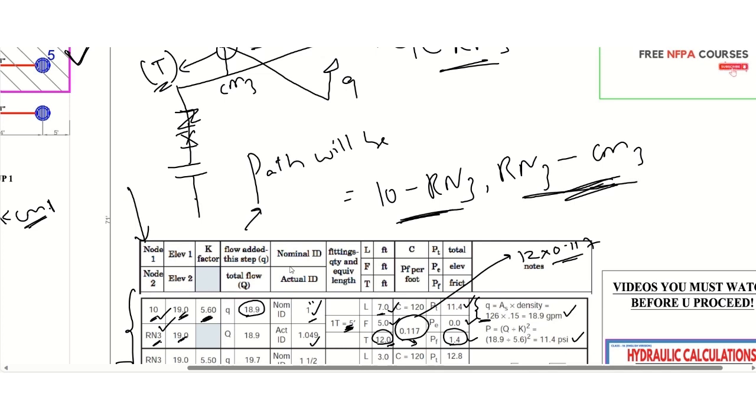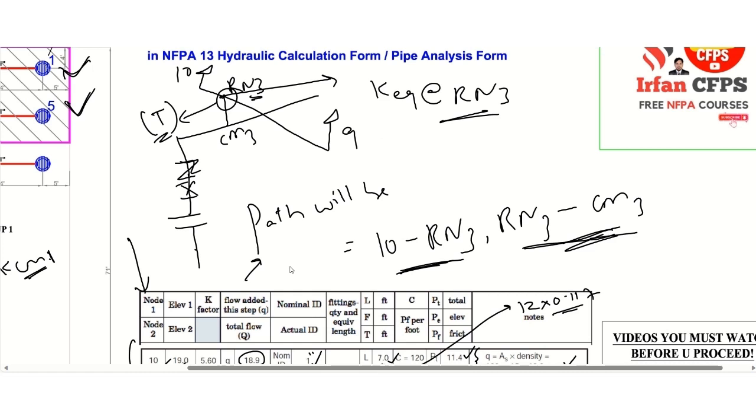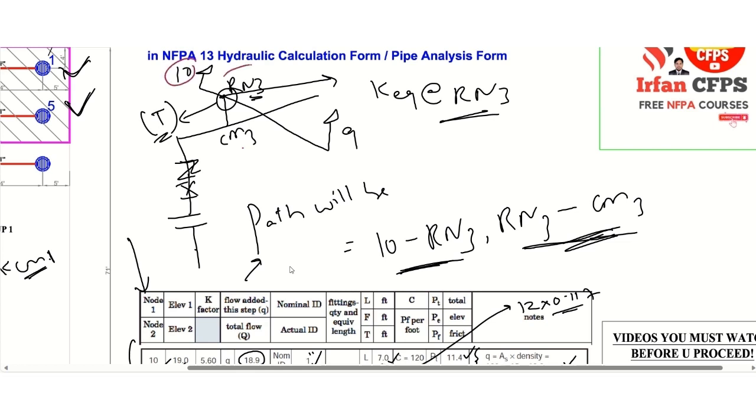So now what we need to do, since we are considering the most challenging path from 10 to RN3, we are going to come back to the primary path from this isometric. If you check here, here 10, RN3 and CM3, this is the primary path. So now we calculated or we have come from 10 to RN3. Now we need to go to CM3. So RN3 to CM3 also we need to calculate. But since here we don't have any sprinkler, so how will we be able to know the K factor? This one we already calculated in our last step when we did 9 to RN3 calculation. So now you understand why we are calculating the equivalent K factor.